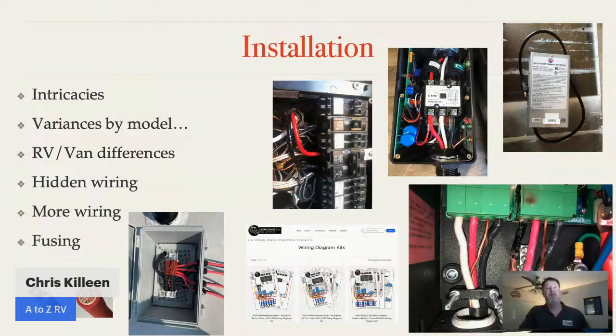Typically when distributors see this, only maybe half an inch is stripped off that line when it's supposed to be 0.7 or more. Obviously, you don't want too much more because you don't want a whole bunch of exposed line coming out. But 0.7 is the minimum, and that's to get it up into those clips and get a good return on the neutral. Otherwise, it'll burn out like you just seen.